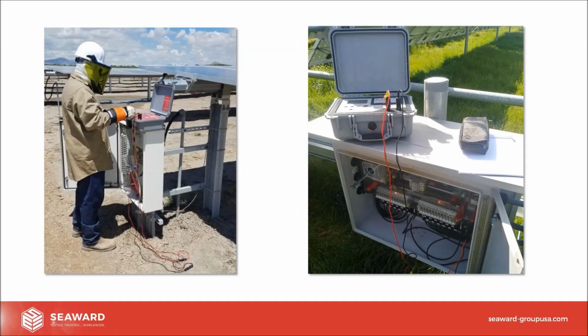So I have a question here from Laurent: is this device better suited to plus 22 solar module strings than using the PV200? I would say that's a very good question. Laurent's question is based on the length of the string, it really depends on what voltage the panels are. So 23 panels at say 50 volts, that would be quite high, but generally anything over 1,000 we don't want to be using the PV200 for that, that would definitely be the Solar Utility Pro.